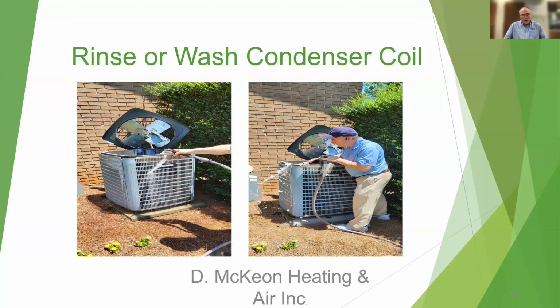Now the photo on the right is where we take the fan off the top of the unit, and then we use the water hose from the inside out. Now anything that's impacted in the fin pack is being pushed out of the fin pack and out of the unit. So that is the best way to wash a coil down right there.